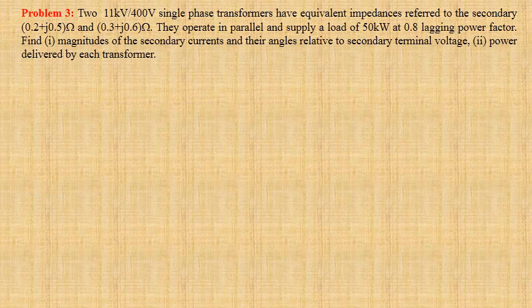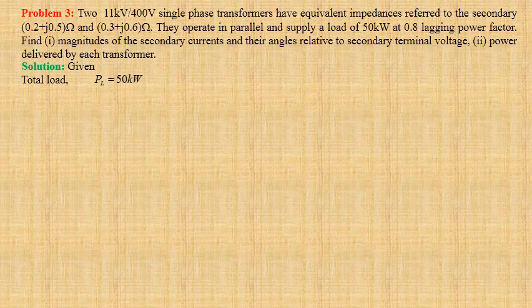Two 11 kV by 400 volt single-phase transformers have equivalent impedances referred to the secondary side of 0.2 plus J0.5 ohm and 0.3 plus J0.6 ohm. They operate in parallel and supply a load of 50 kilo watt at 0.8 lagging power factor. We have to determine the magnitudes of the secondary currents and their angles relative to secondary terminal voltage, and also the power delivered by each transformer. Total load PL equals 50 kilo watt. Load power factor cos phi L equals 0.8 lagging.